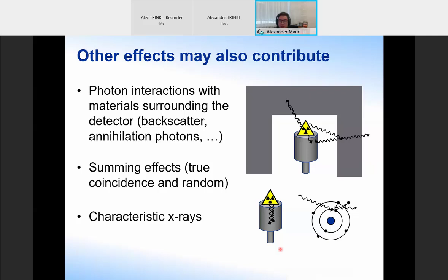So, wow, that was a lot of theory about photon interactions. Now, let's see how this can translate into some actual spectra. Here is a typical spectrum from a cesium-137 source. Cesium-137 has a single primary gamma ray emission at 661.6 kiloelectron volts, and you'll see here in the spectrum, you indeed get one peak at that energy.